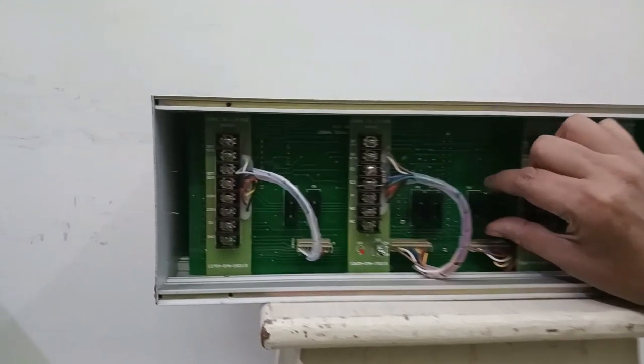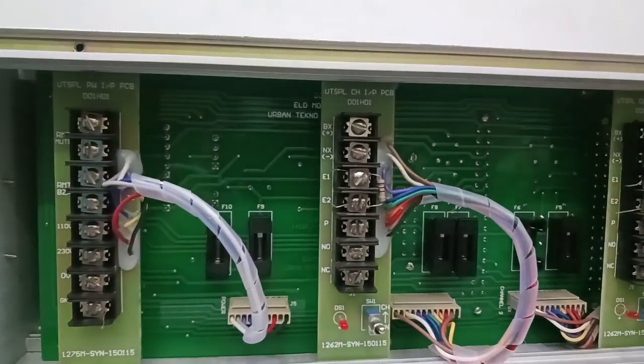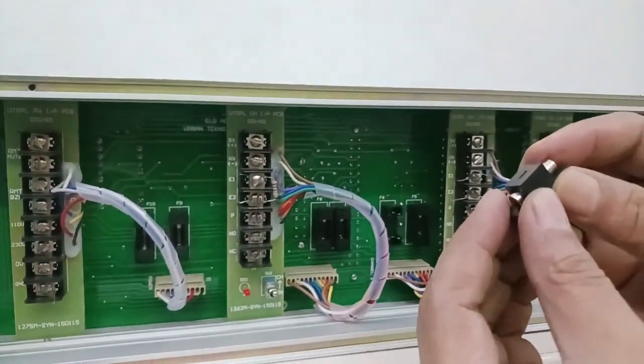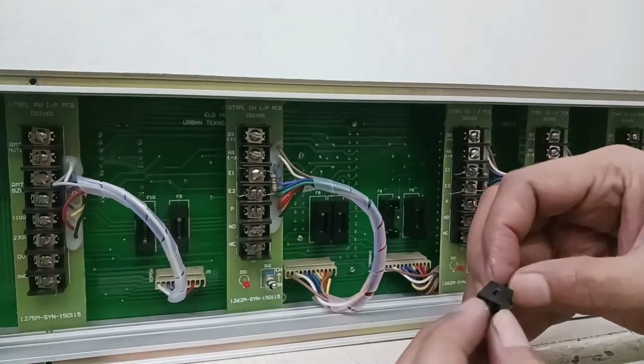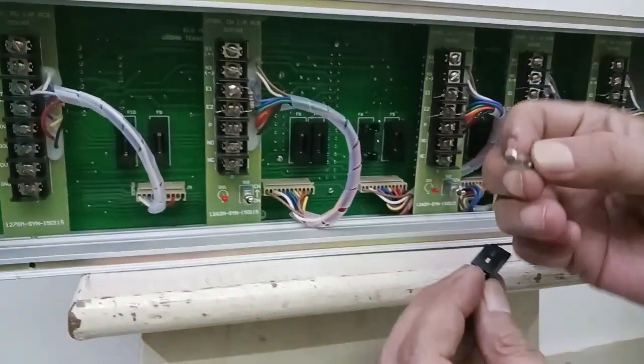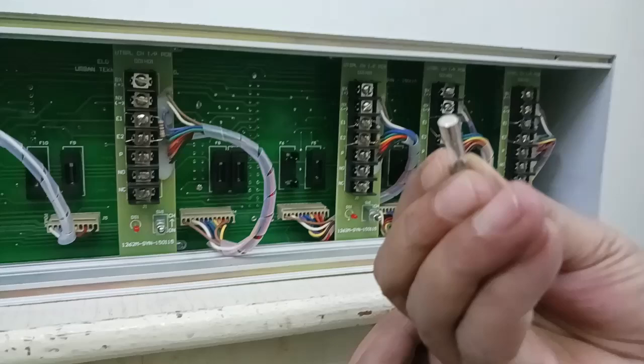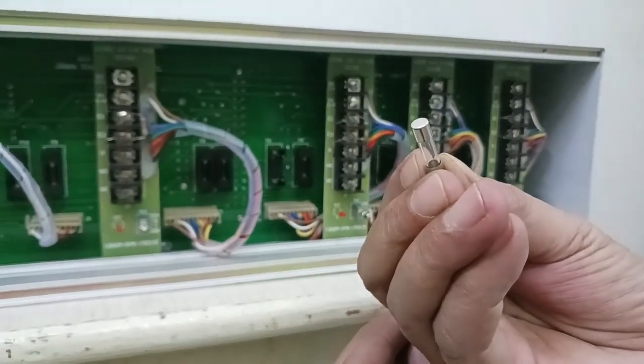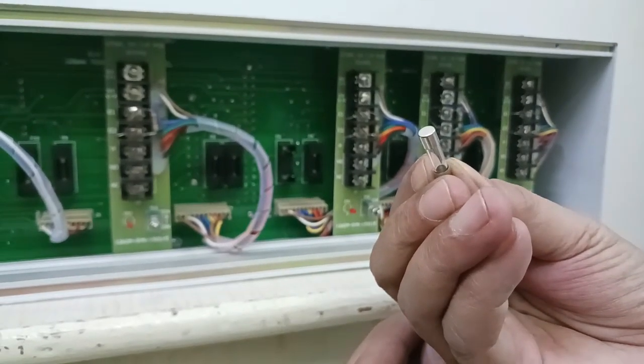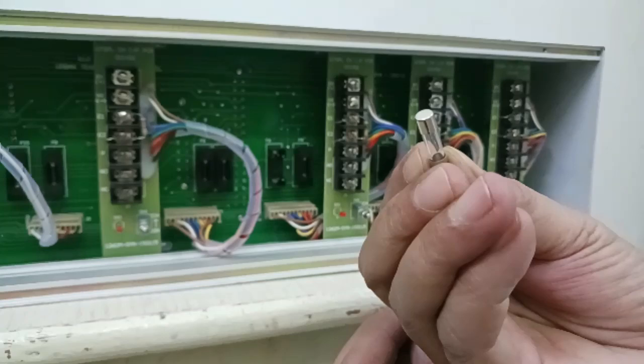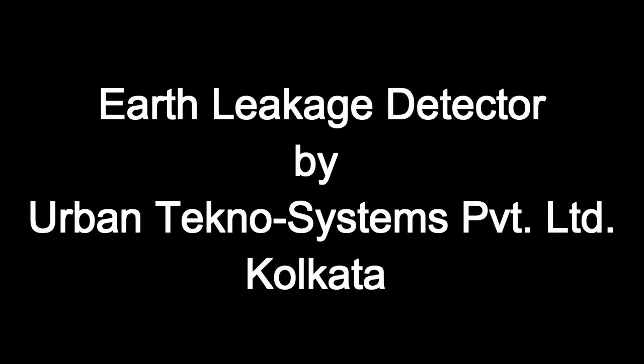Each channel's NX and BX inputs are protected through fast blow type fuses of 100 mA 250 volt. If you see that the bus bar present LED indicator is not glowing, then check the corresponding fuses. If it's found blown, replace the fuse with exact value and exact type only. With this we conclude video on Earth Leakage Detector by Urban Tekno-Systems Private Limited.